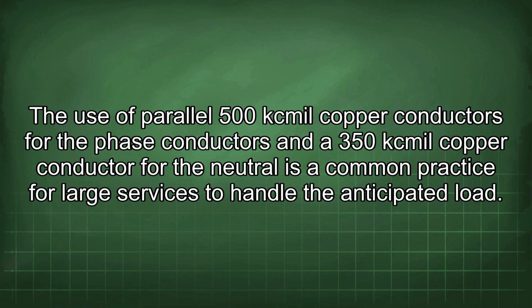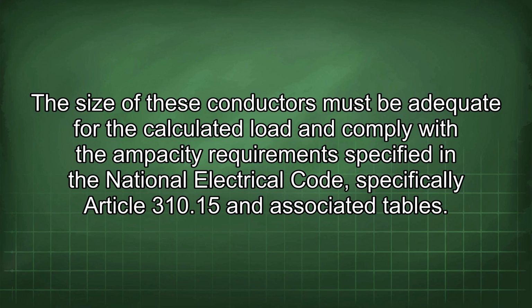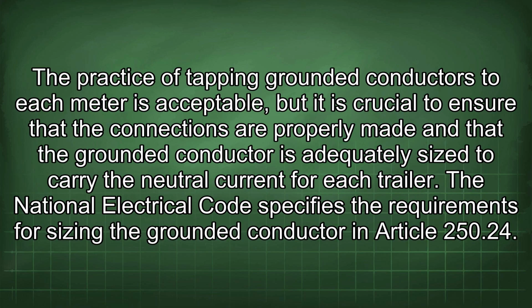The use of parallel 500 kcmil copper conductors for the phase conductors and a 350 kcmil copper conductor for the neutral is a common practice for large services to handle the anticipated load. The size of these conductors must be adequate for the calculated load and comply with the ampacity requirements specified in the National Electrical Code, specifically Article 310.15 and associated tables. The practice of tapping grounded conductors to each meter is acceptable, but it is crucial to ensure that the connections are properly made and that the grounded conductor is adequately sized to carry the neutral current for each trailer. The National Electrical Code specifies the requirements for sizing the grounded conductor in Article 250.24.